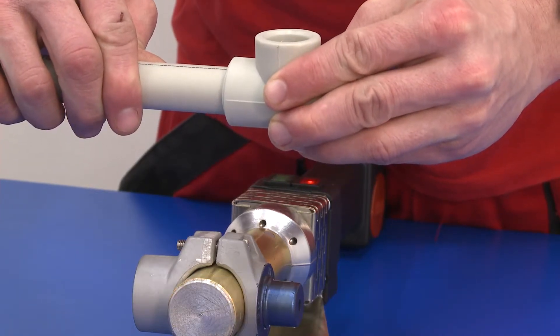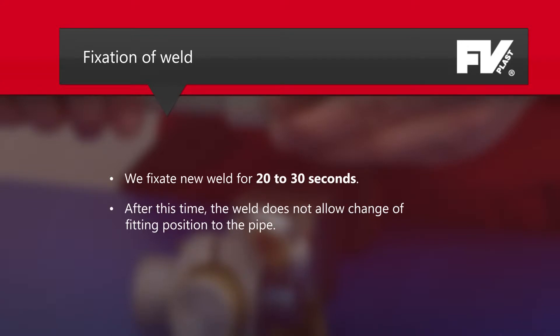The new weld must be fixed for 20 to 30 seconds when a partial cooling occurs. After this time the weld does not allow change of position or fitting to the pipe.